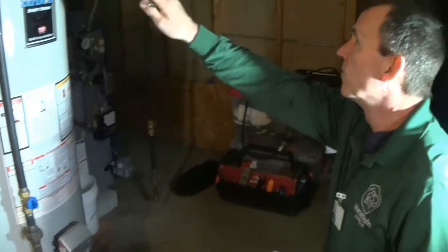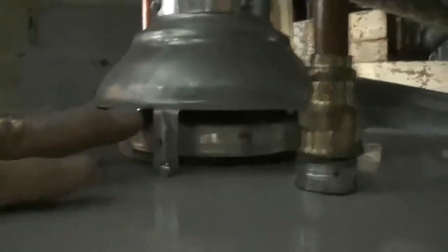We would drill the holes that we need for this test. They happen to already be drilled, but in the case of the domestic hot water heater, and they're actually all behind here, we're not going to need to drill a hole for carbon monoxide because we're just going to measure that by getting our probe down inside here before air mixes in. We would drill a hole up here after this elbow, which I'm feeling for right now.